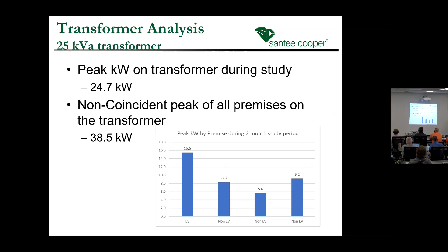They were running at 13.4 kW, with three others right around 4 kW. So these non-EV customers weren't significantly high at that point—they got up to 8, 5, and 9—so they weren't anywhere close to their max demand during that peak on the transformer.